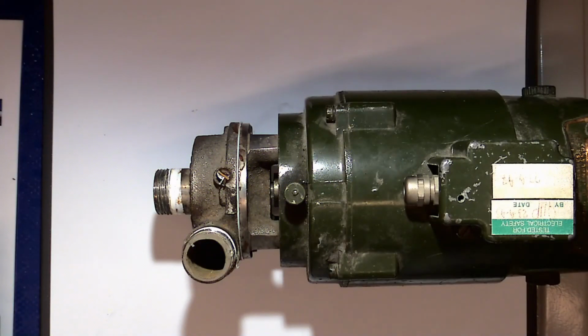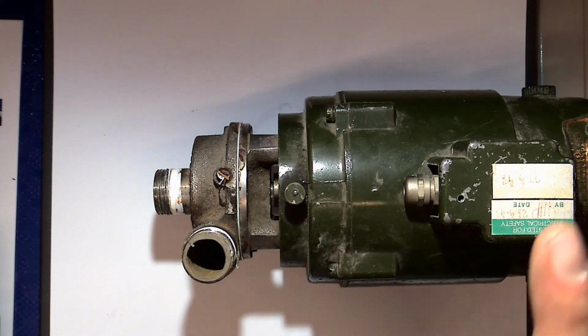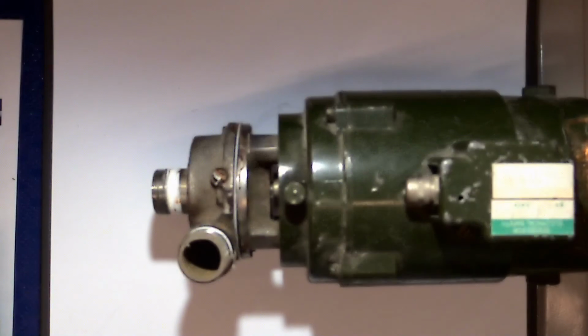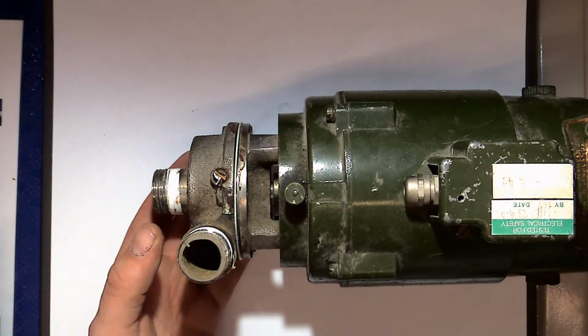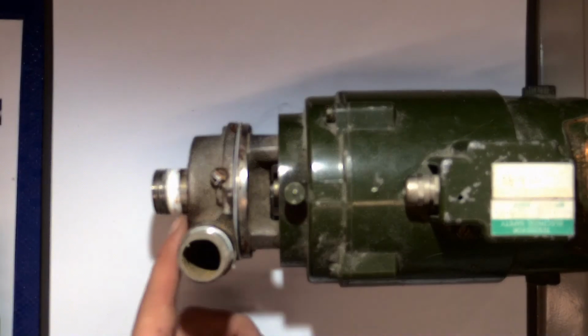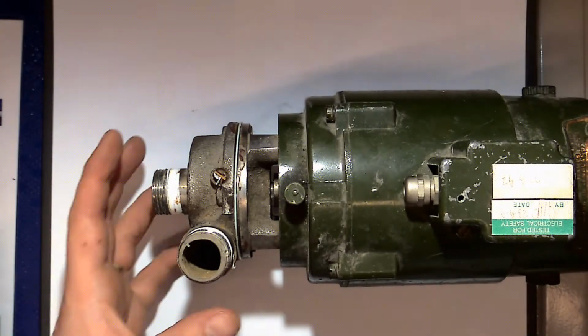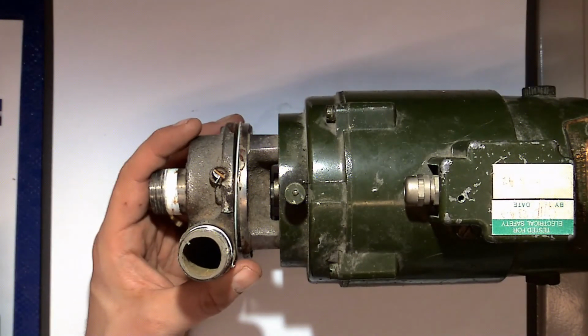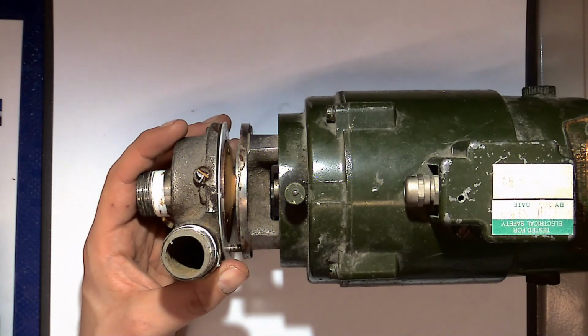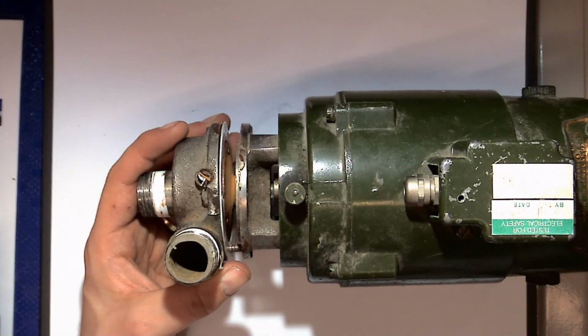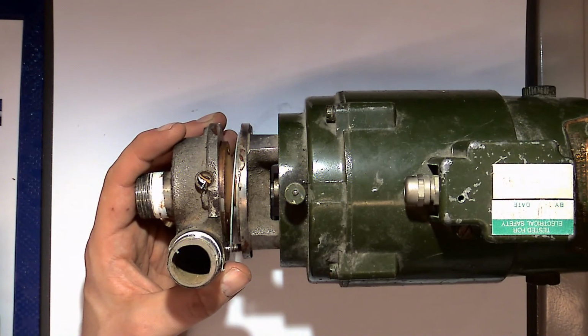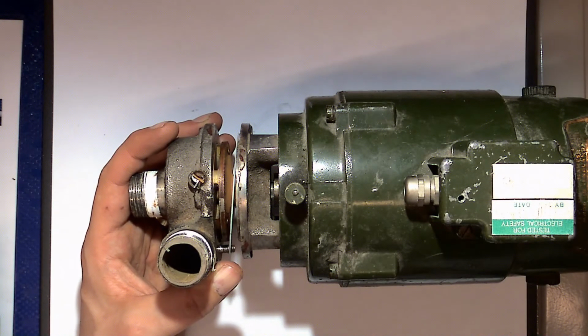Okay, so here we have the first pump, centrifugal pump, impeller pump, motor on this side, pump head here. You'll see that there's some white tape, PTFE tape. That's to prevent leaks obviously, but it is crucially the liquid that was being pumped does not eat PTFE tape.